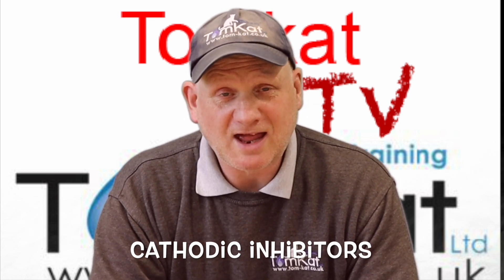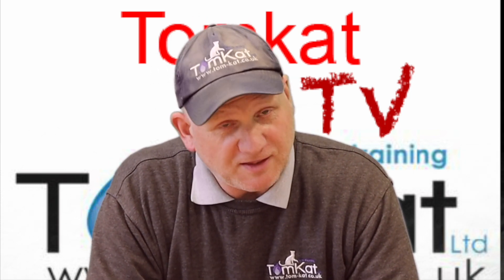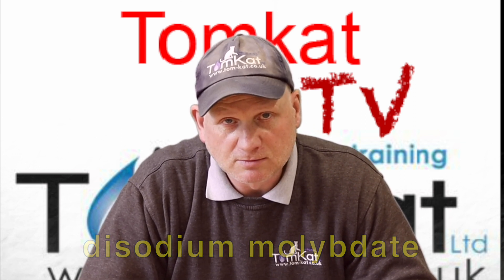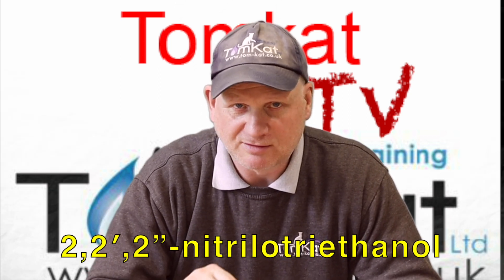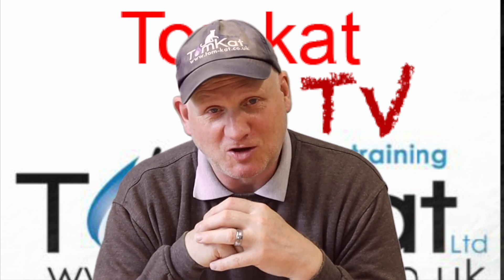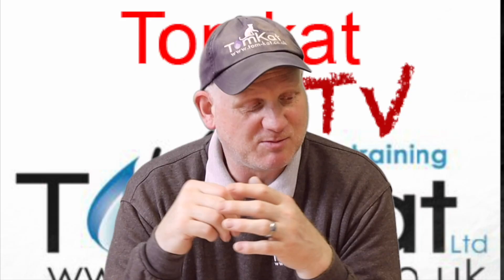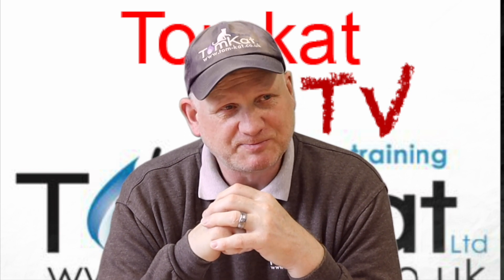As well as the three different types, there are four different chemicals used: potassium tetraborate tetrahydrate, sodium molybdate, sodium nitrate, and 2,2',2''-nitrilotriethanol. Those are the main types of inhibitor. On the bottles it doesn't actually tell us what chemicals are in there - just the manufacturer's name and the standards - so when we come to test this water we don't exactly know what we're testing for.